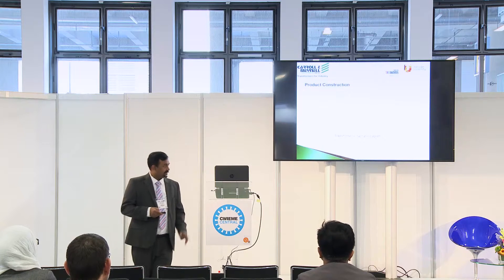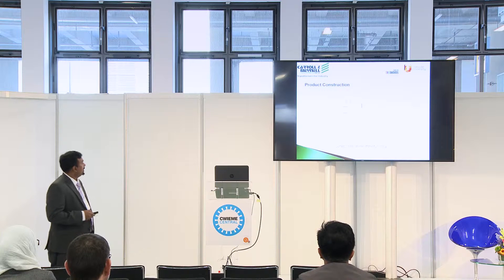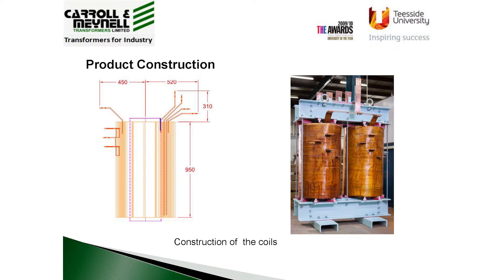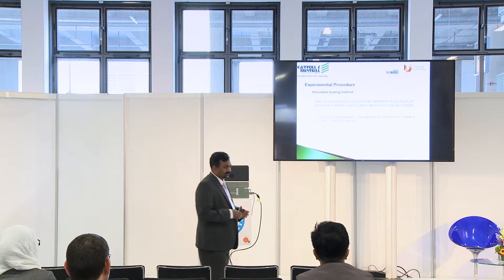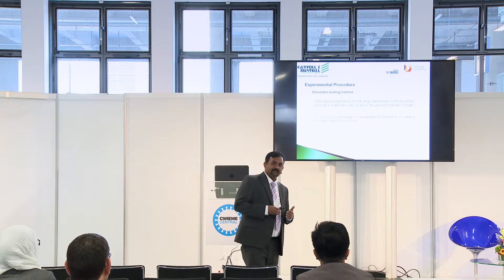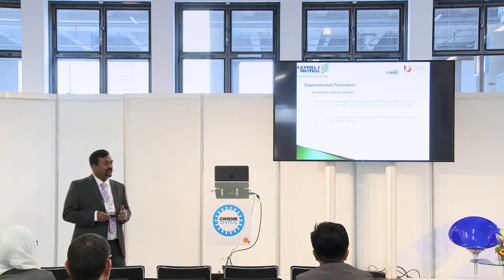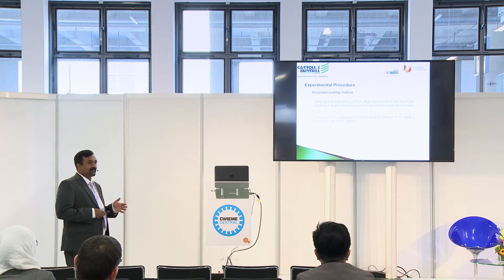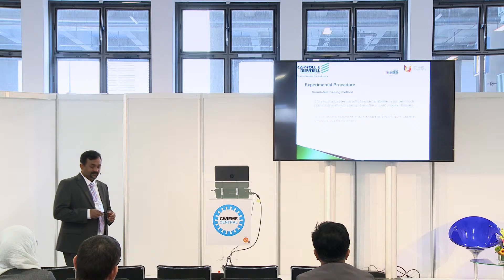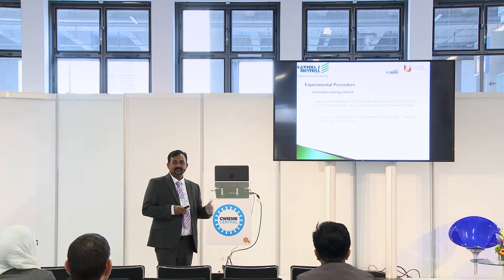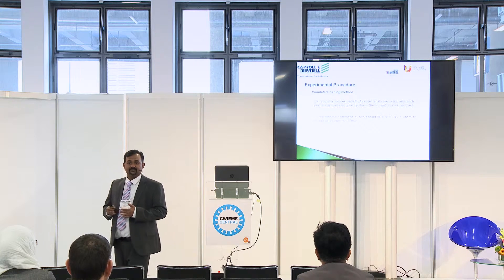Moving into the product construction — this is the schematic of the transformer, with one primary and two secondaries; the ideal structure was of course a UI core configuration. This is the schematic of the initial coil design and this is how it looked when constructed. Regarding simulated loading: we wanted to make sure that temperatures do not reach excessive levels, but you obviously can't load such a high-power transformer under normal laboratory conditions — single phase 1 MVA is quite a high power level to achieve in a laboratory.